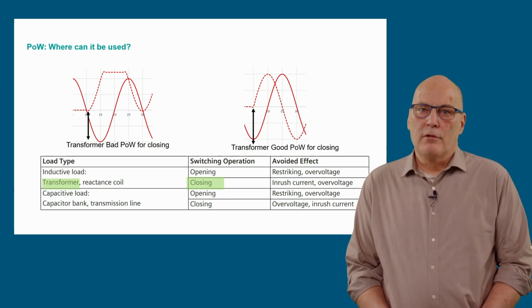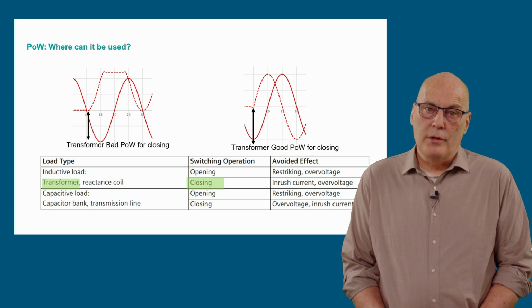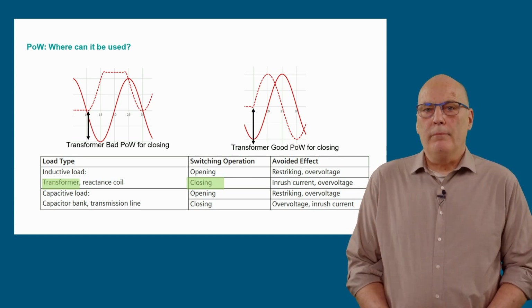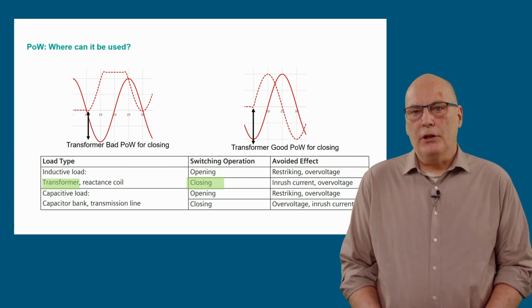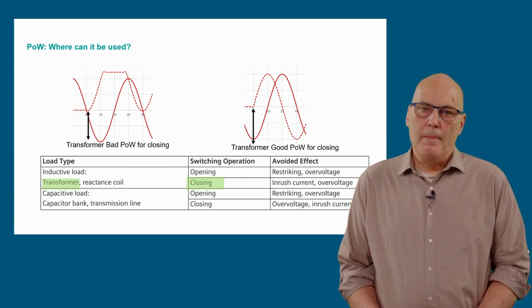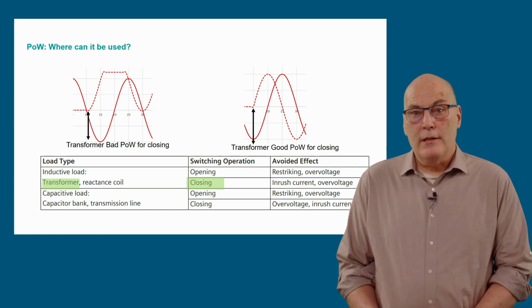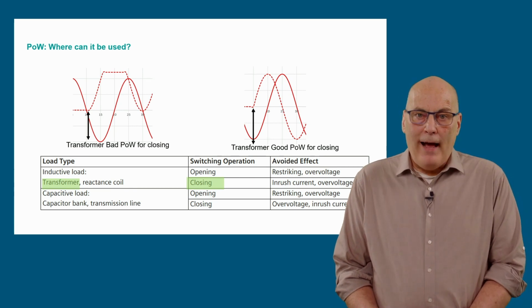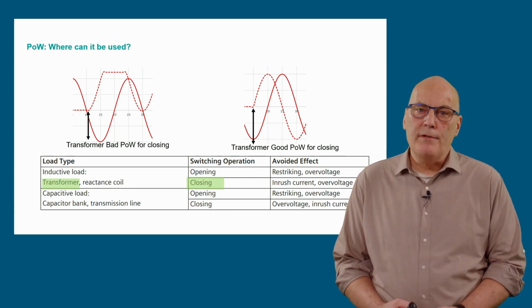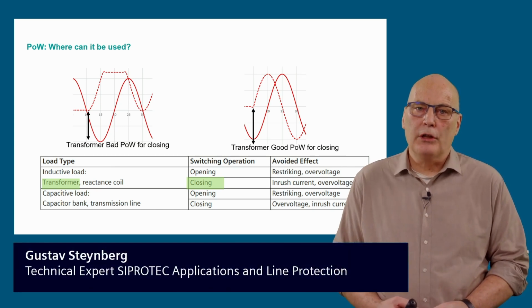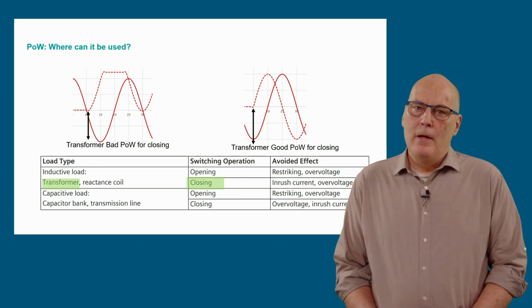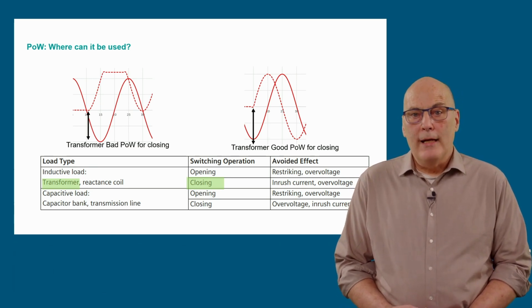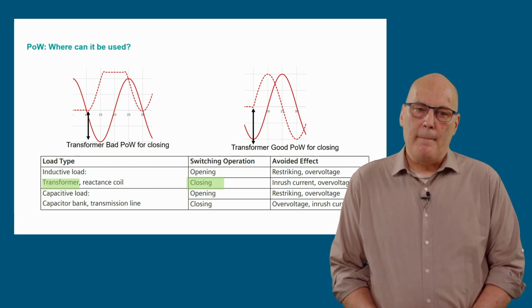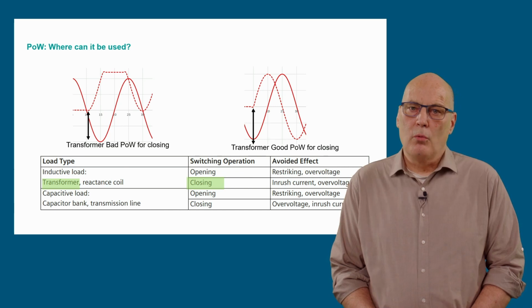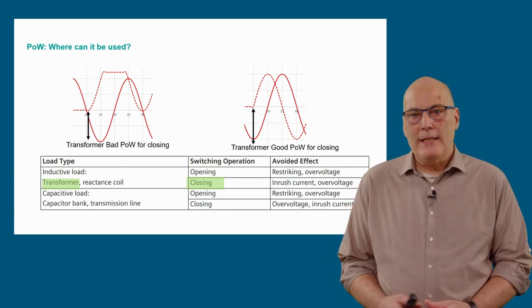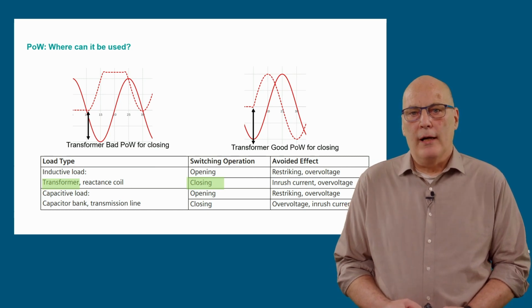Inductive loads, such as transformers and reactors, typically have iron cores. When these iron cores saturate during closure, as shown on the left, there will be a severe inrush current during saturation. If the inductive load is closed by point-on-wave, as shown on the right-hand side, the flux dashed line will have no offset and will therefore have no inrush current as it does not go into saturation. Point-on-wave switching, closing and opening is therefore of particular interest for the cases listed here. Inductive loads, transformers and reactors, capacitive loads, capacitor banks, and to a lesser degree, transmission lines and cable feeders.